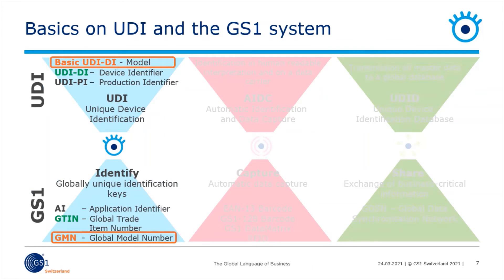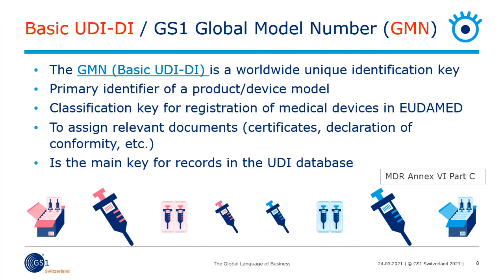On the next few slides, I will talk about the basic UDI-DI. We saw the basics of identification and that we need a GS1 company prefix. The basic UDI-DI — in the GS1 system it is called GMN, Global Model Number — is required in the UDI as a unique classification key for medical devices in Eudamed. It is the first key you will enter in Eudamed. It is used for the unique identification of product models.